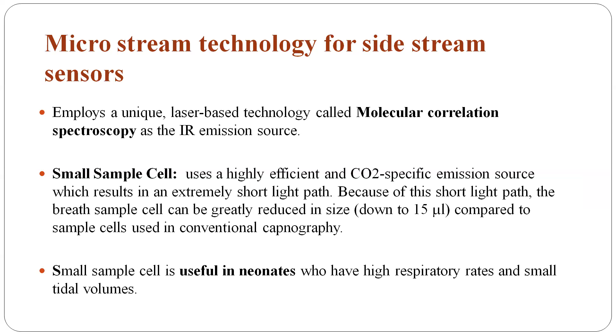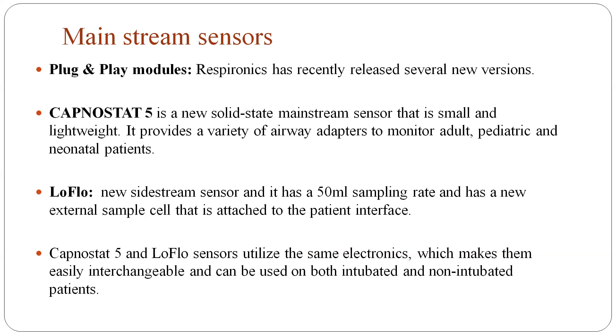In mainstream sensors, there is a plug and play module introduced by Respironics, and there are two versions. Capnostat 5 is a new solid state mainstream sensor that is small and lightweight. It provides a variety of airway adapters to monitor adult, pediatric and neonatal patients. Another one is LoFlo, a new side stream sensor. It has a 50 ml sampling rate and a new external sample cell that is attached to the patient interface. These Capnostat 5 and LoFlo sensors utilize the same electronics, which makes them easily interchangeable, and they can be used in both non-intubated and intubated patients.